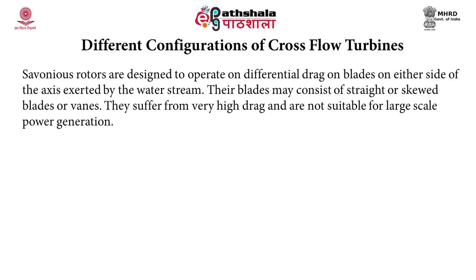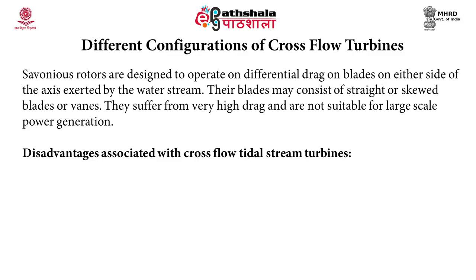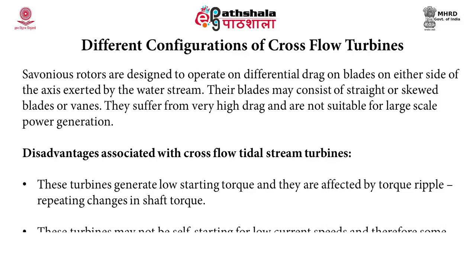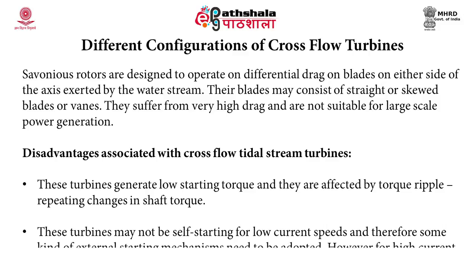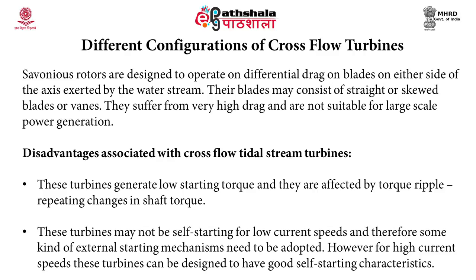Savonius rotors suffer from very high drag and are not suitable for large-scale power generation. The disadvantages associated with cross flow tidal stream turbines include low starting torque as they are affected by torque ripple — repeating changes in shaft torque. These turbines may not be self-starting for low current speeds and therefore some kind of external starting mechanism needs to be adopted. However, for high current speeds these turbines can be designed to have good self-starting characteristics.